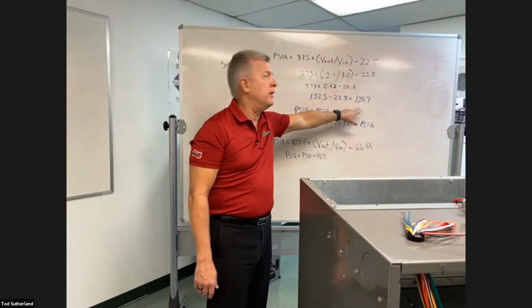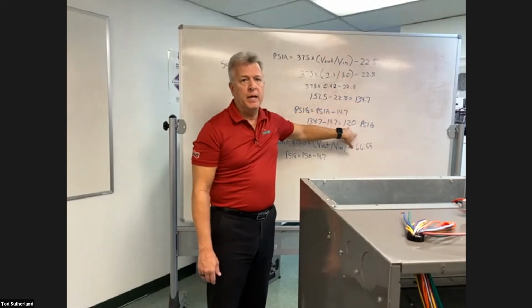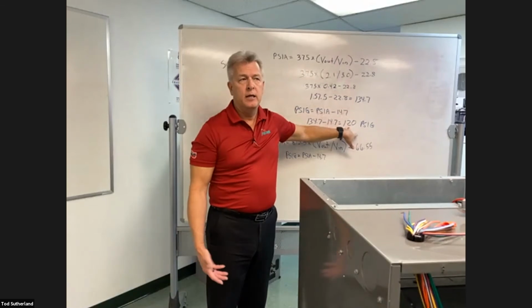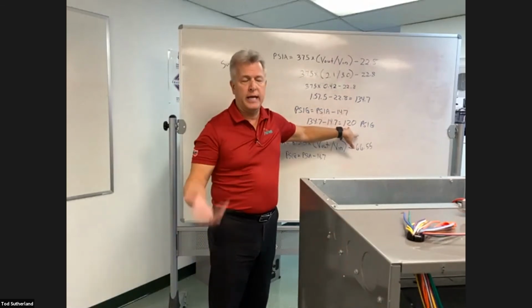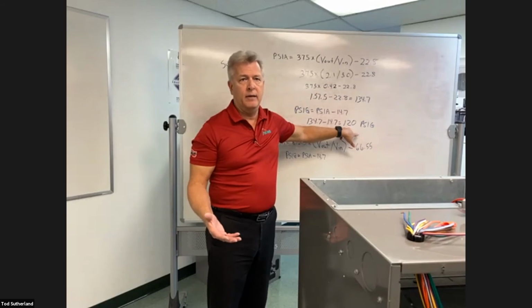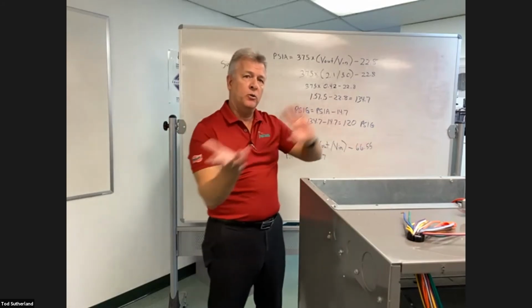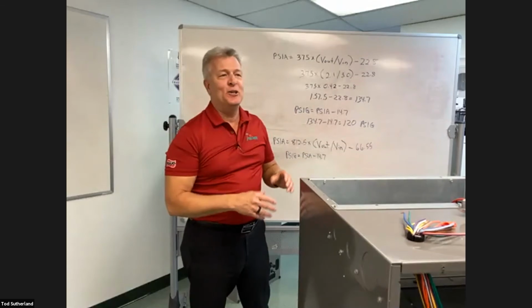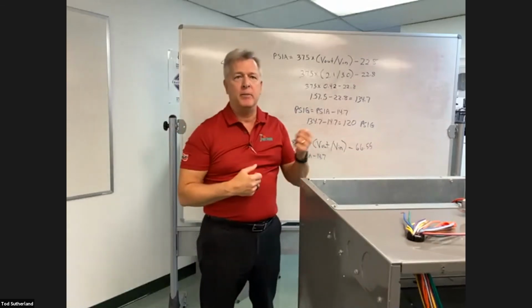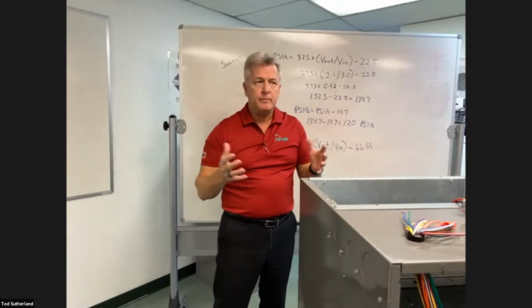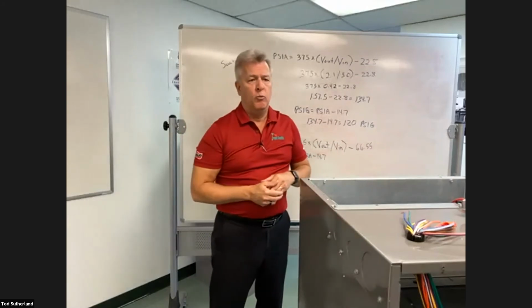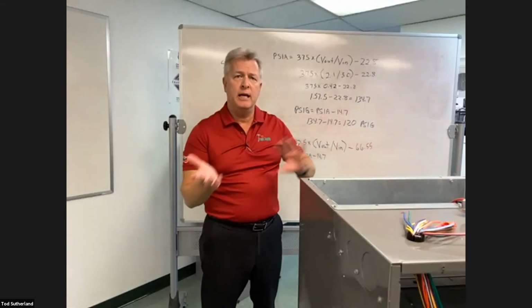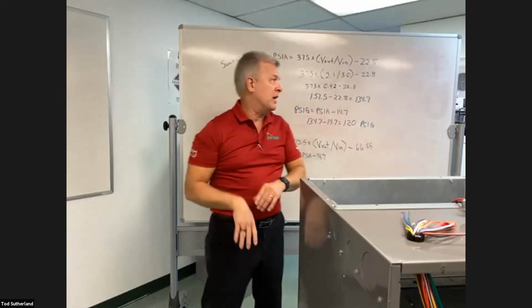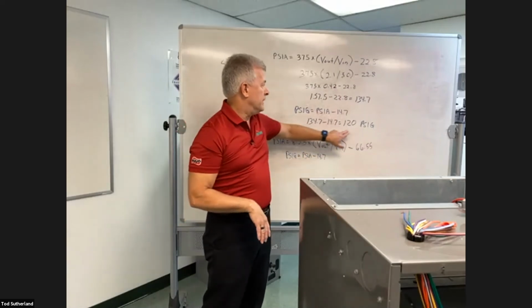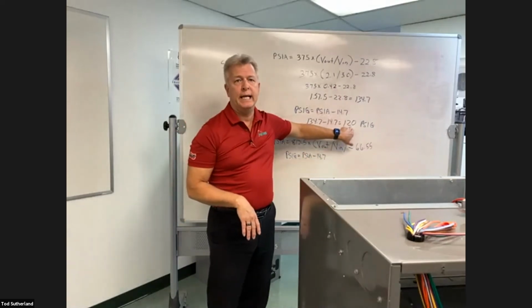And of course, this is probably going to end up reading different than what you have on your gauges, because all the gauges are not going to be calibrated exactly alike. And we don't want you using gauges, but that's a whole other class. We're going to get you into hopefully using nothing but temperature clamps and hygrometers when you're checking these systems. Once the system's been installed and commissioned, you should never have to put a manifold on it again, but we'll talk about that in another class. But this should be close to what you're reading, okay?